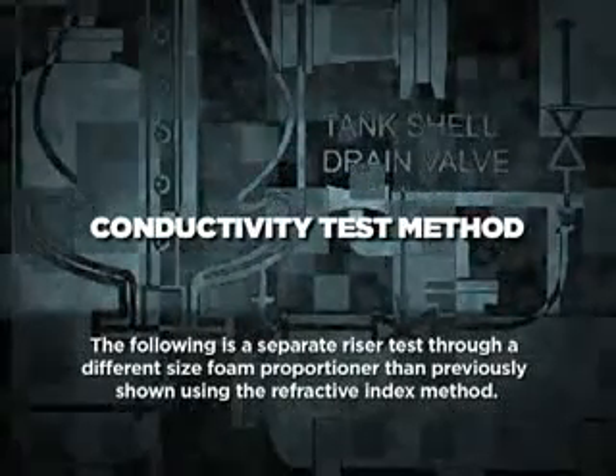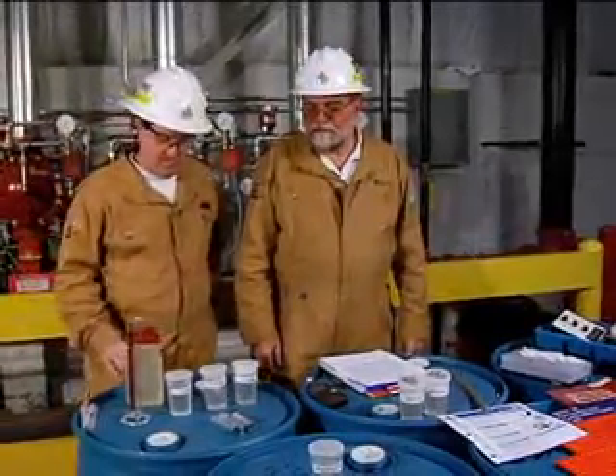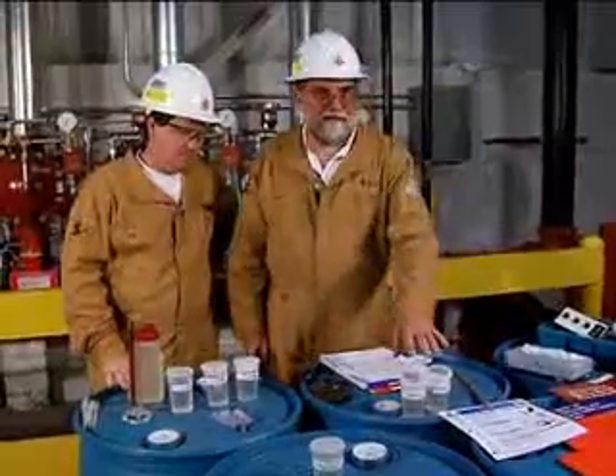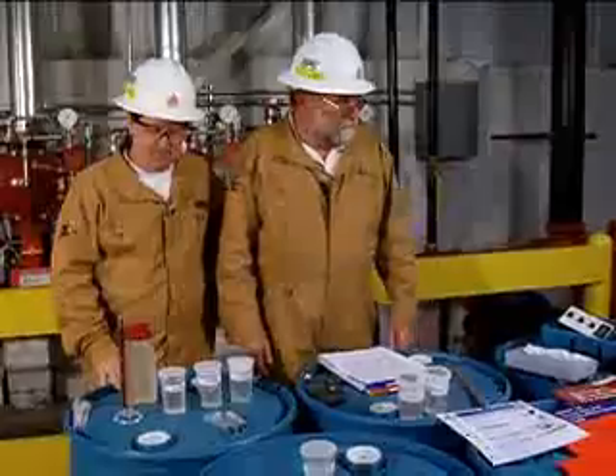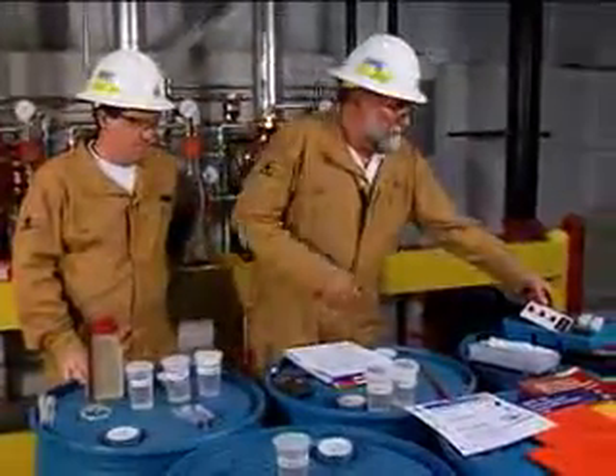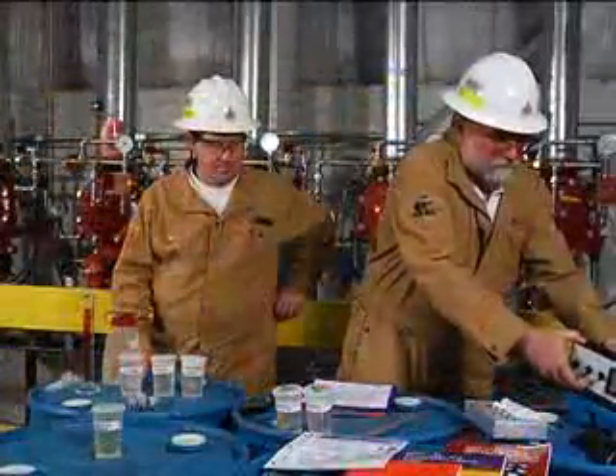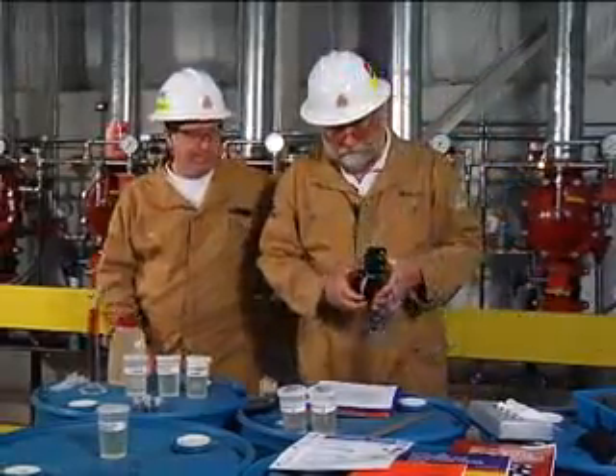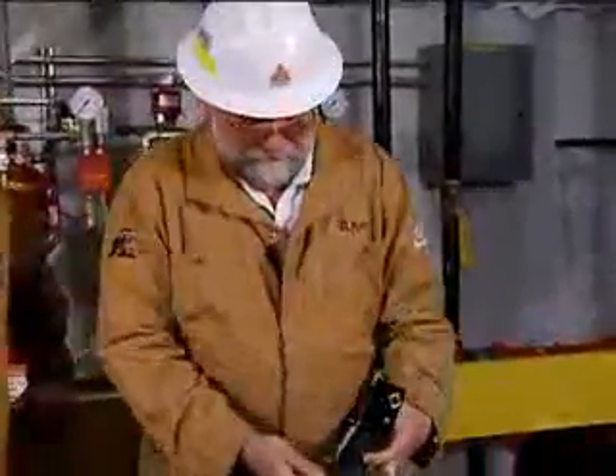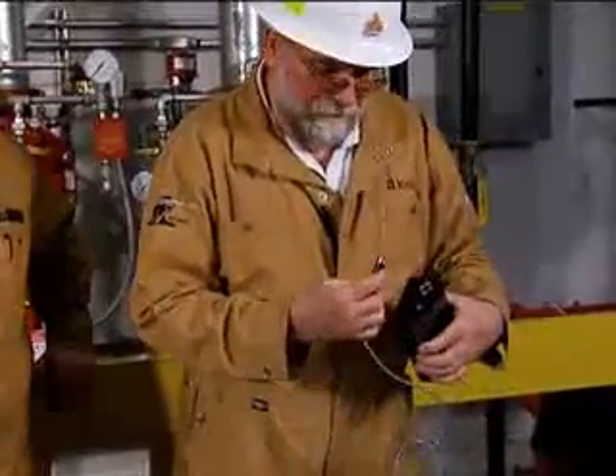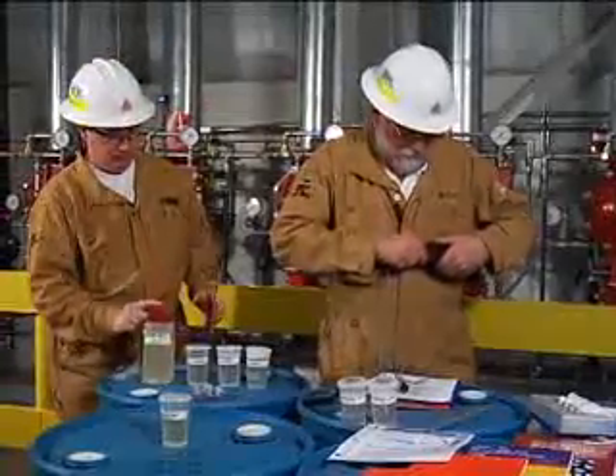Commission testing the Ansul bladder tank. Foam system testing, conductivity test method. Next, we're going to be doing the concentration test on the discharge samples that we pull from the tank and rail car deluge system. To demonstrate using conductivity, here's our conductivity meter. We'll connect our sample probe to the meter.